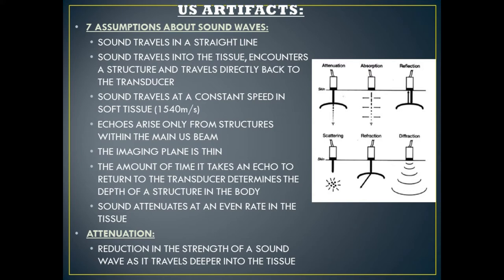The first assumption that an ultrasound machine makes is that sound travels in a straight line. Assumption number two, sound travels into the tissue, encounters a structure, and travels directly back to the transducer. Assumption three, sound travels at a constant speed in soft tissue — 1540 meters per second.